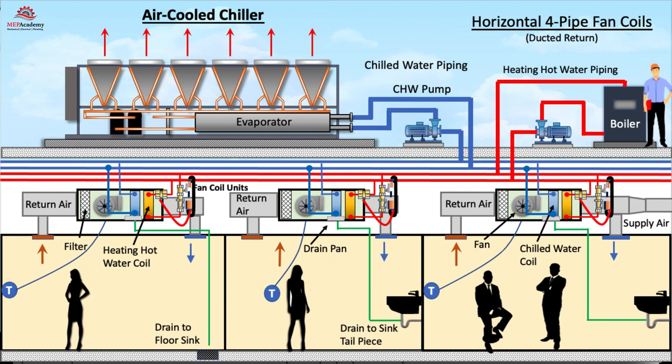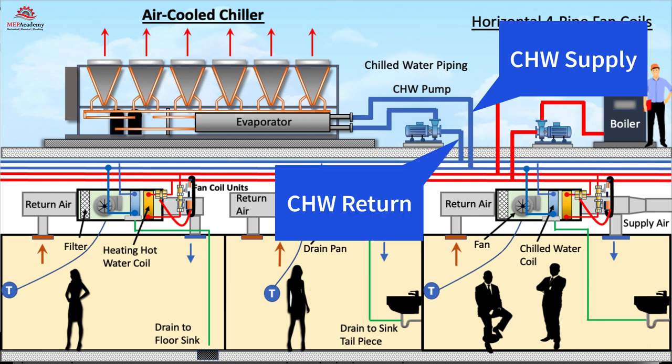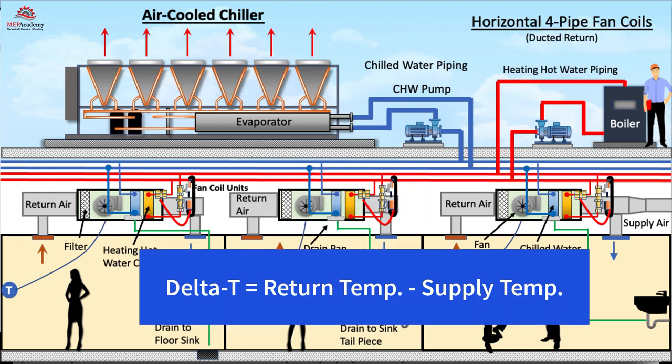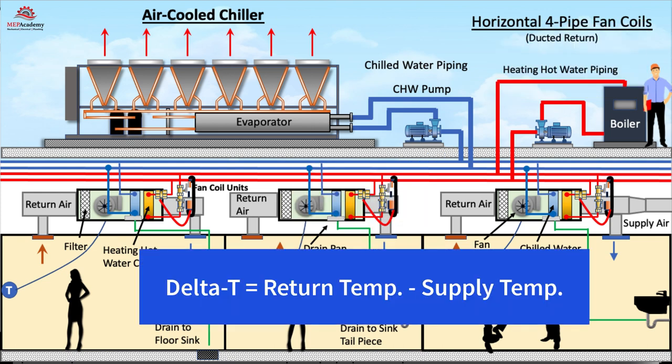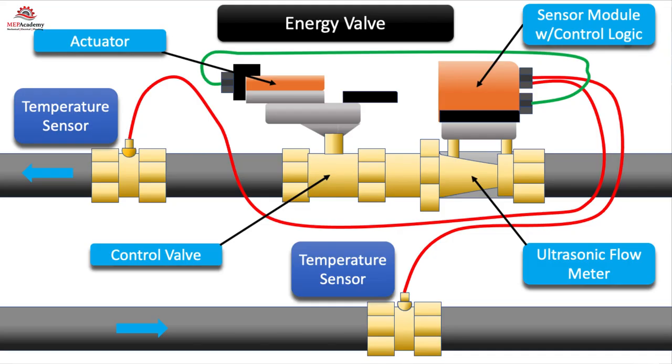In order to do this, we need the water to increase in temperature as much as possible between the chilled water supply and chilled water return. This is indicated by the delta T, the difference in temperature between the supply and return. A higher delta T requires less to be pumped through the system saving on pump energy. In order to avoid providing too much flow to a coil or heat exchanger, an energy valve can ensure optimization of system flow.